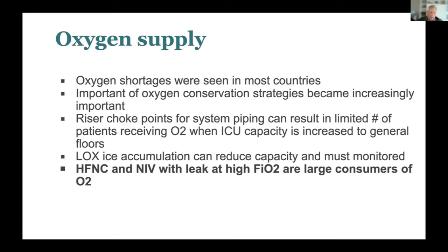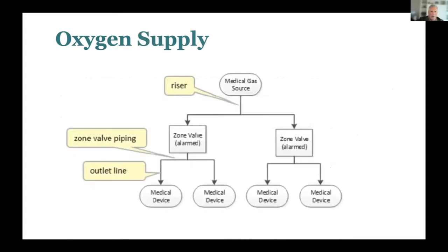I'll show you some pictures of how, when you're using liquid oxygen, this can create an issue for delivery—I've only seen it happen a couple of times. Believe it or not, high flow nasal cannula and non-invasive ventilation with a leak at higher FiO2s are the largest consumers of oxygen. In the interest of time: when the pipes come into your hospital from the outside liquid system, they go up or sideways, making them either laterals or risers.